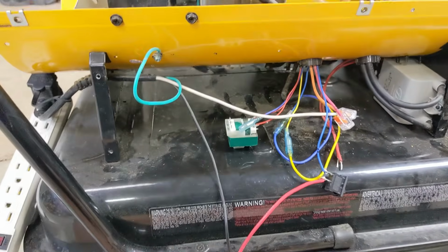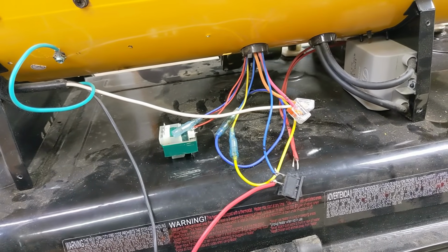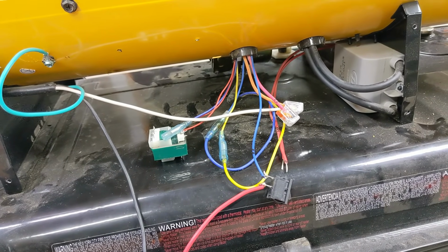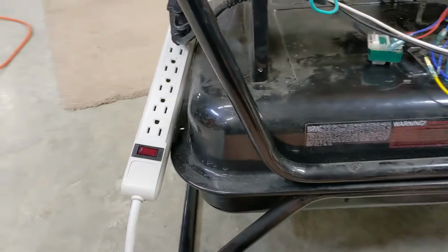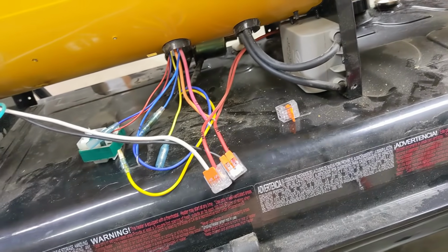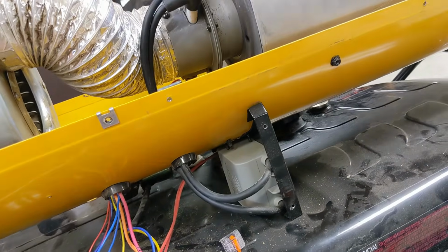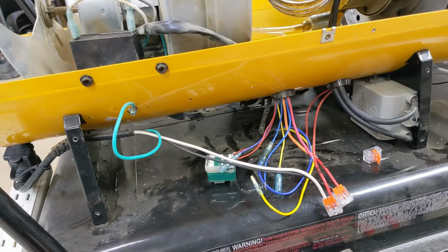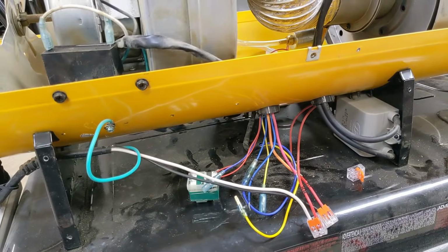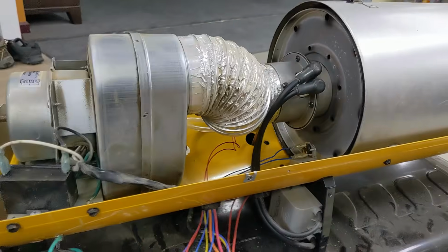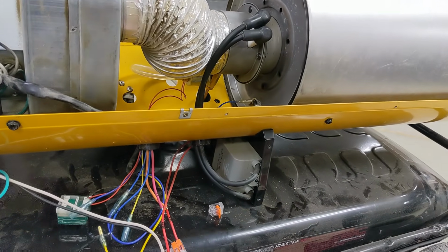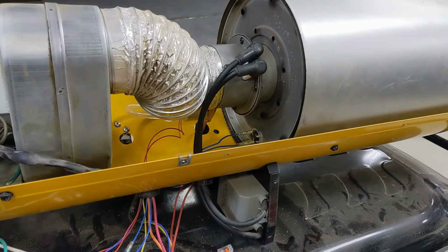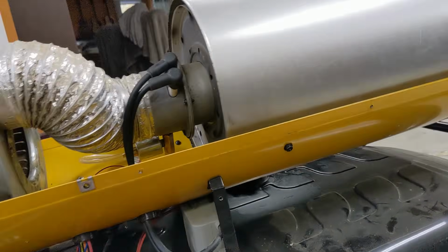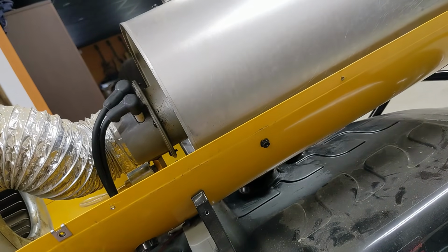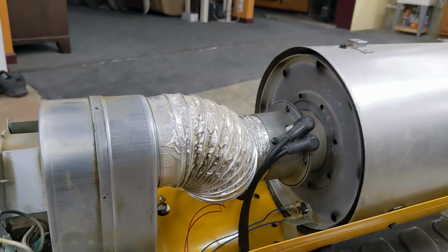Okay, the last thing we got to test is the igniter and the solenoid, that's next. I've got AC going directly to the igniter, so let's test that out. I just ran the fan by itself for a while to clear out any fumes, so it shouldn't ignite anything, but let's test it. I heard it, did you hear it? Can't see it, but I'm pretty sure that's fine, that's what it sounds like when it's running.